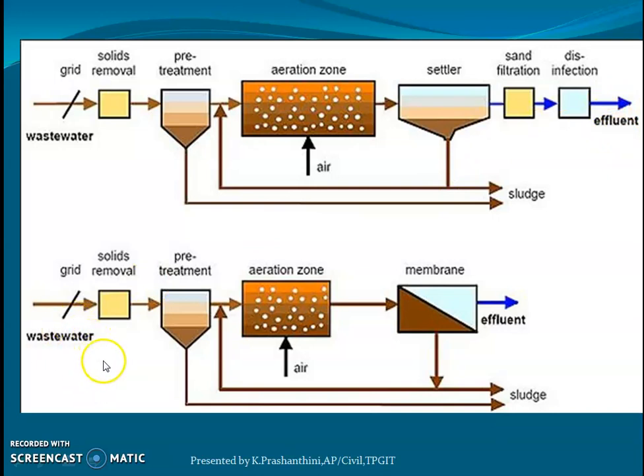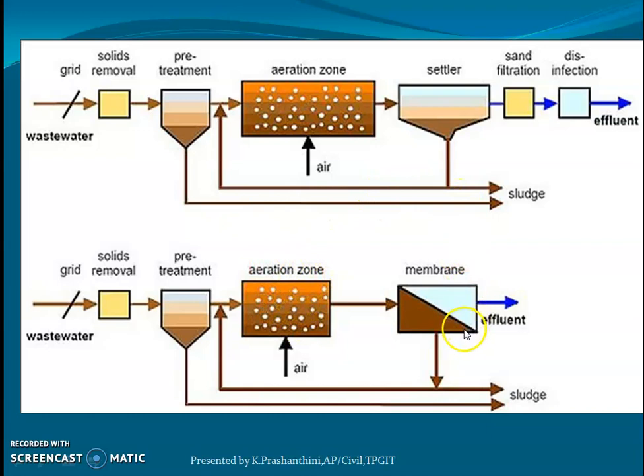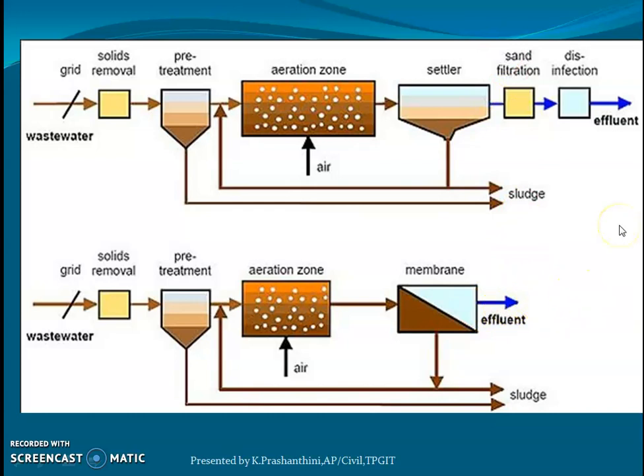In the MBR-based STP, the wastewater after passing through screens and grit chambers enters the primary sedimentation tank or pre-treatment unit, and then moves to the aeration zone. Here, the secondary sedimentation tank and sand filter are replaced by very thin membranes, and the treated effluent from the membrane is disinfected or directly discharged into nearby water bodies.